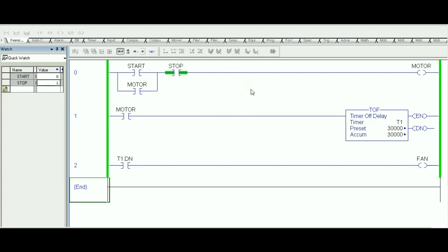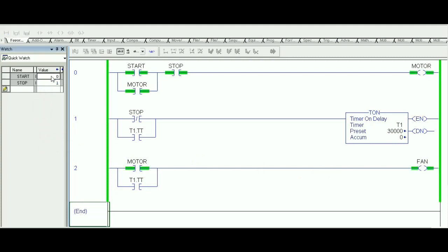Now let's build the same problem using TON to see how it differs. Since we're using TON, we use the Stop contact to trigger the TON timer, and we latch it with Timer1.TT to keep it alive — because Stop is a momentary switch and the timer needs to remain on for 30 seconds. Timer1.TT also drives the fan. When Start is pressed and released, the motor is on, and we use the motor contact to drive the fan — so both start immediately when Start is pressed.